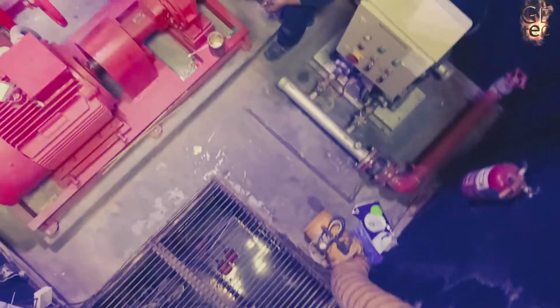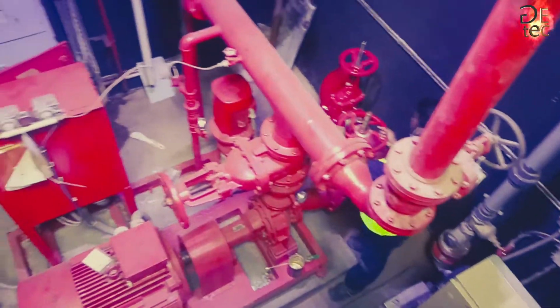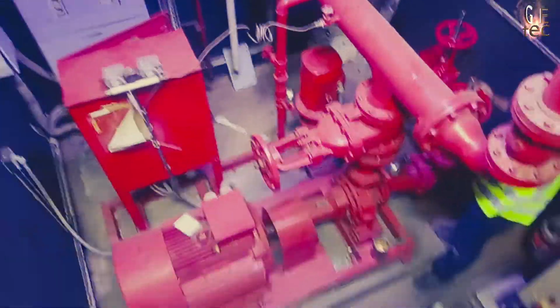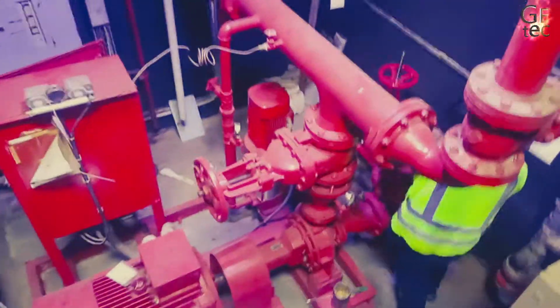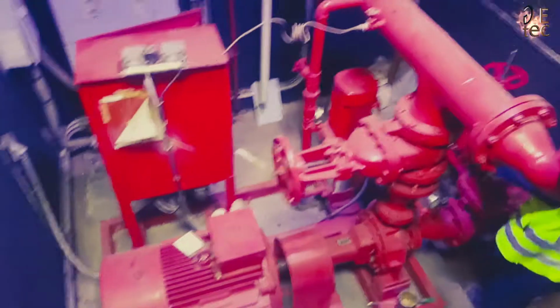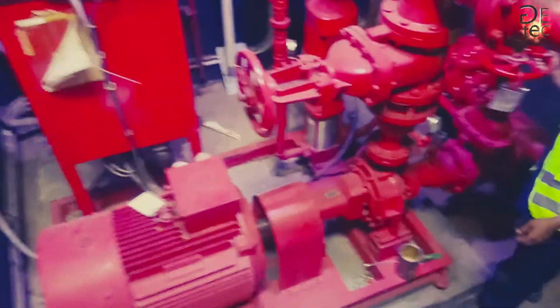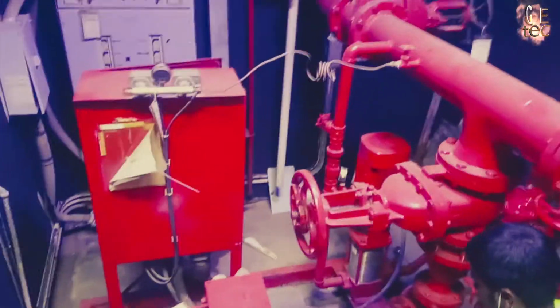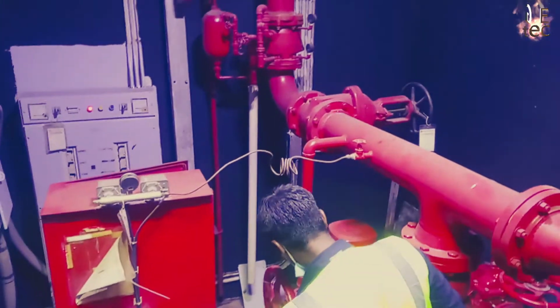The main code that governs fire pump installations in North America is the National Fire Protection Association's NFPA 20 standard for the installation of stationary fire pumps for fire protection. Fire pumps function either by an electric motor or a diesel engine, or, occasionally, a steam turbine. If the local building code requires power independent of the local electric power grid, a pump using an electric motor may utilize, when connected via a listed transfer switch, the installation of an emergency generator.